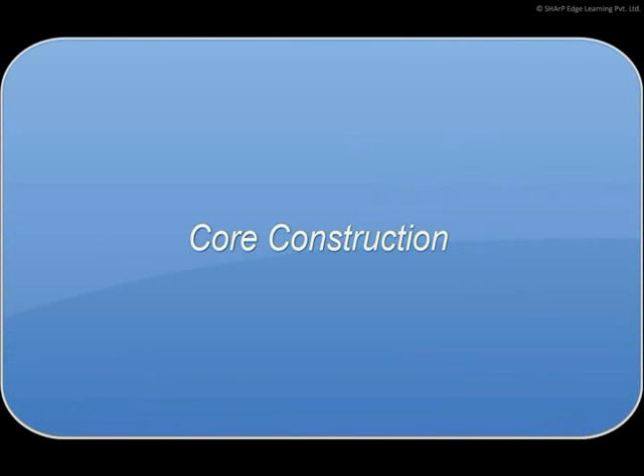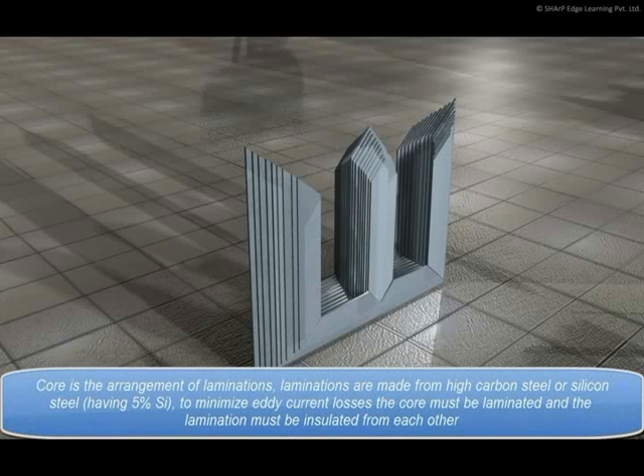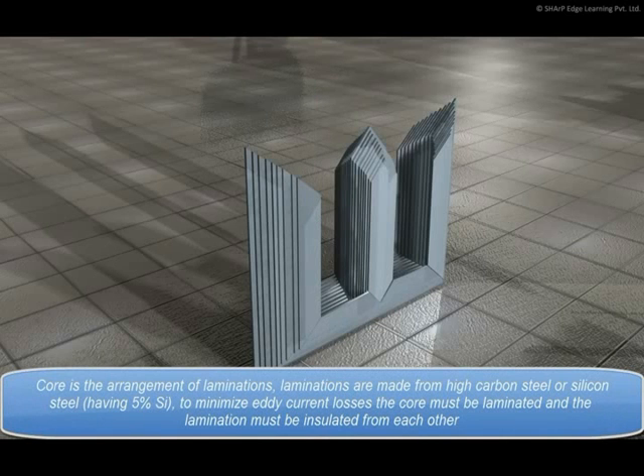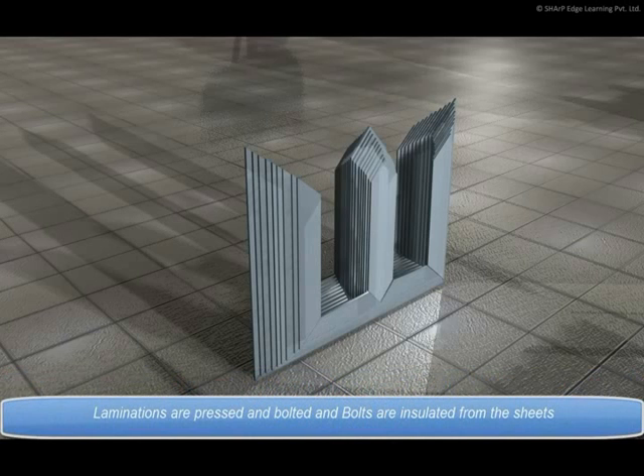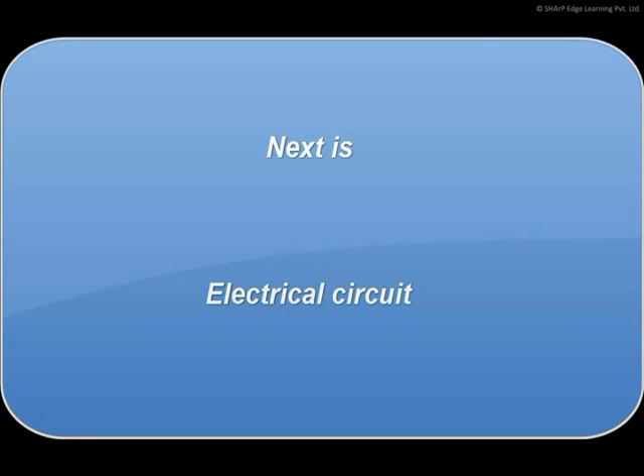Core Construction. The core is the arrangement of laminations. Laminations are made from high carbon steel or silicon steel having 5% silicon to minimize eddy current losses. The core must be laminated and the laminations must be insulated from each other. Laminations are pressed and bolted, and the bolts are insulated from the sheets.